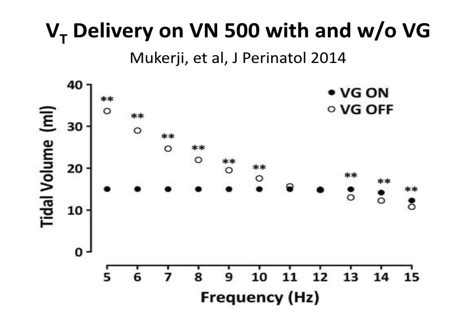So basically, it's not a piston oscillator. It doesn't have a big loudspeaker like the SensorMedics. The way it generates positive deflection is it squirts as much gas as needed down the inspiratory limb, so opens all or some of the solenoids. And there's a maximum of about, I think, 120 liters that you can shoot down there.